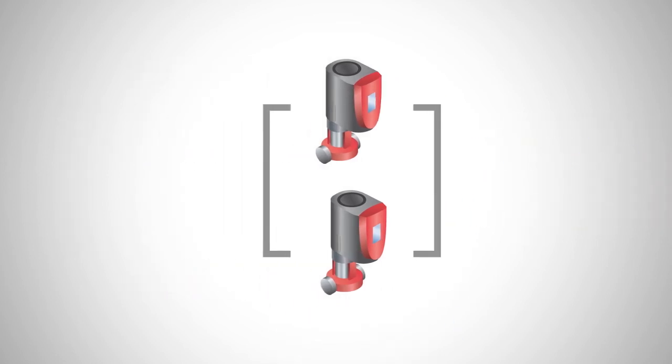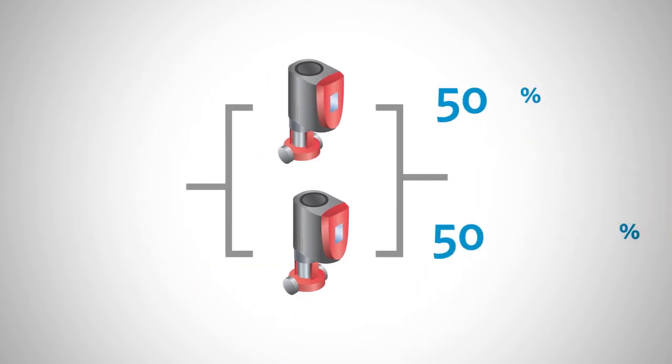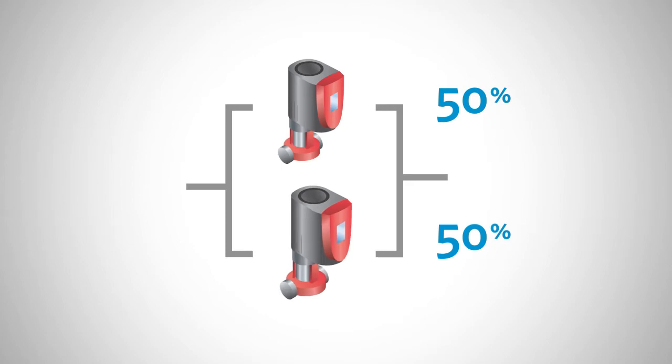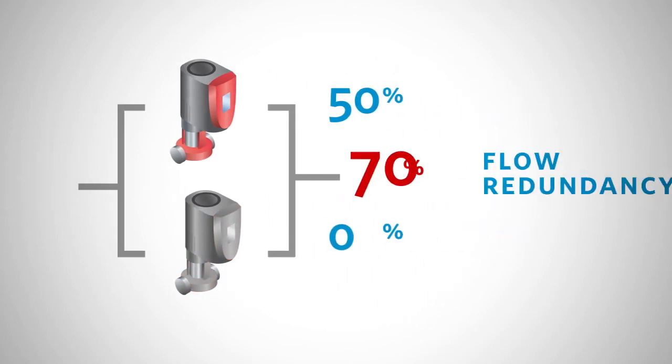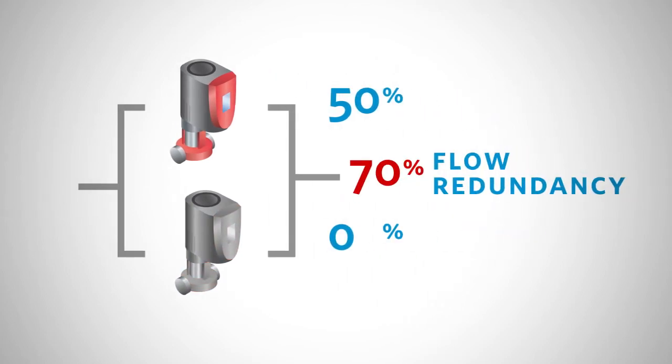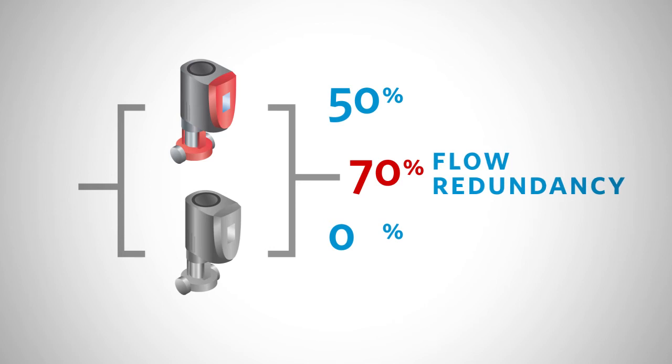For example, a flow capacity split of 50-50 would result in each of the two pumps being sized for 50% of the design flow. If one of the pumps is offline for service, the remaining pump could still provide as much as 70% of the design flow rate.